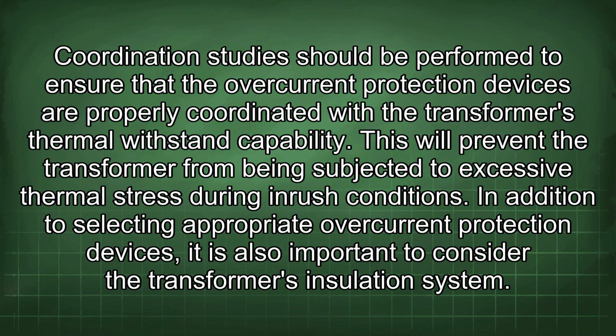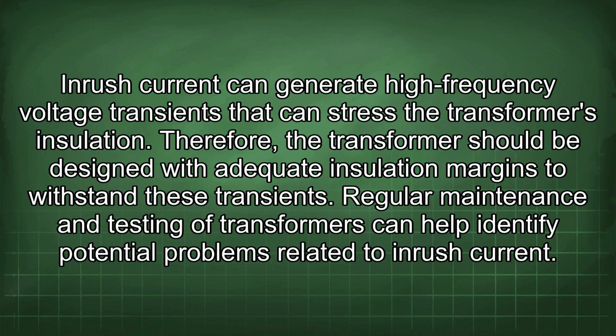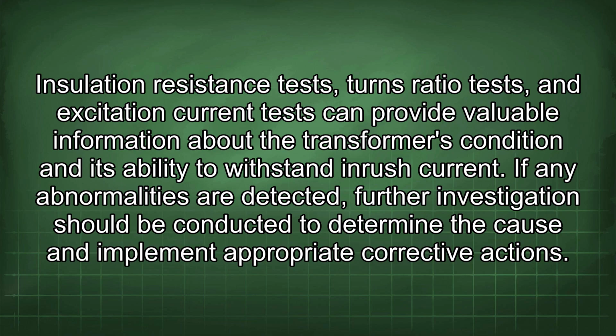In addition to selecting appropriate overcurrent protection devices, it is also important to consider the transformer's insulation system. Inrush current can generate high-frequency voltage transients that can stress the transformer's insulation. Therefore, the transformer should be designed with adequate insulation margins to withstand these transients. Regular maintenance and testing of transformers can help identify potential problems related to inrush current. Insulation resistance tests, turns ratio tests, and excitation current tests can provide valuable information about the transformer's condition and its ability to withstand inrush current. If any abnormalities are detected, further investigation should be conducted to determine the cause and implement appropriate corrective actions.